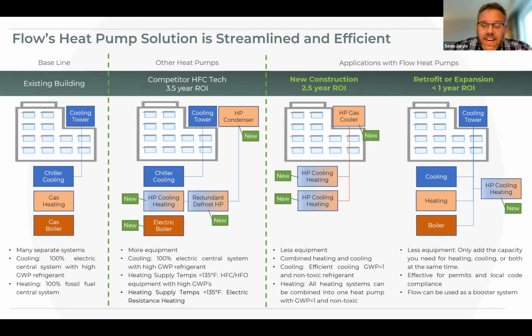A system like this can actually be a one-to-one application with a boiler, and it can replace a chiller. It can allow you to not have that huge expense of redoing the entire inside of your building. And you just keep using your existing equipment, and maybe just put an outdoor air unit in a parking lot, do a changeover piping, and change it over in a week or a weekend if you're really on top of your game. Now that's pretty amazing. But the next part about that that's even better, because you can do simultaneous heating and cooling on one device, or either or heating and cooling, is you can combine operations.